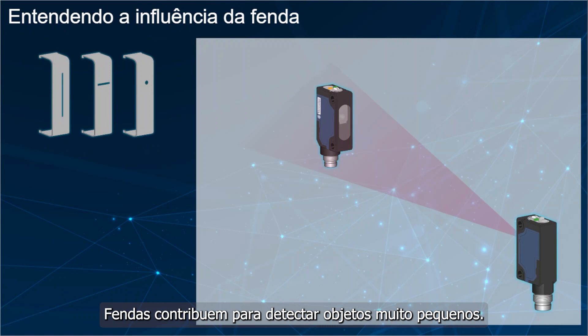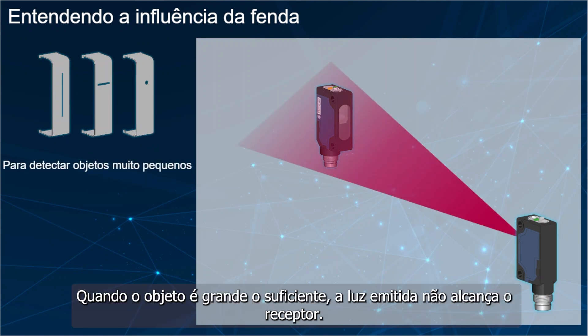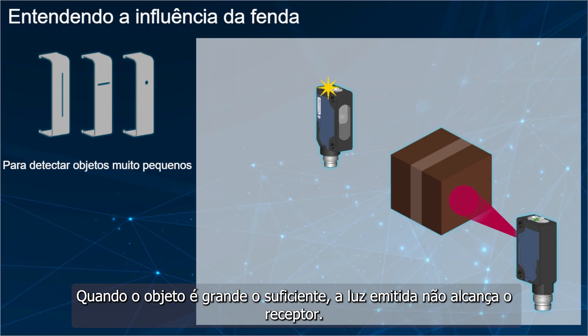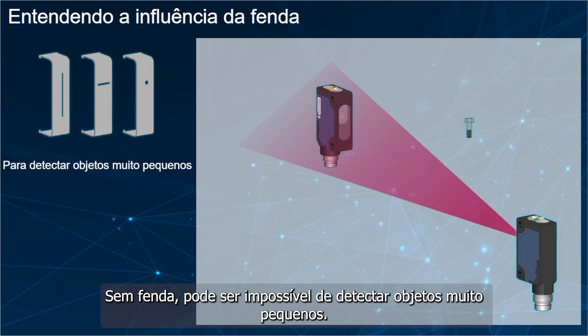The slits contribute to detect very small objects. When the object is big enough, the emitted light does not reach the receiver. A small object lets too much energy reach the receiver. Without slits, it can be impossible to detect very small objects.